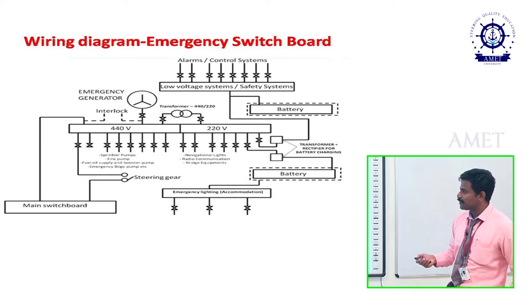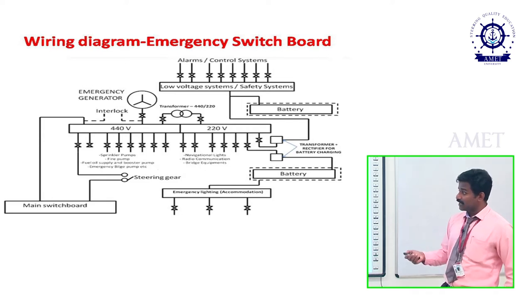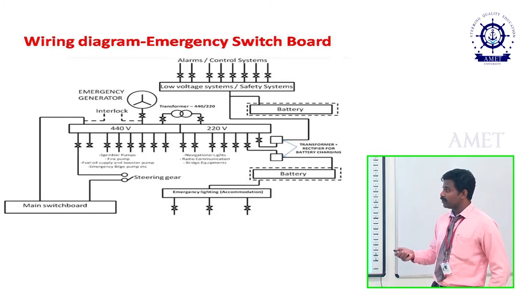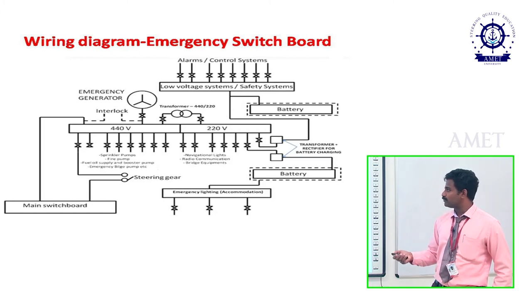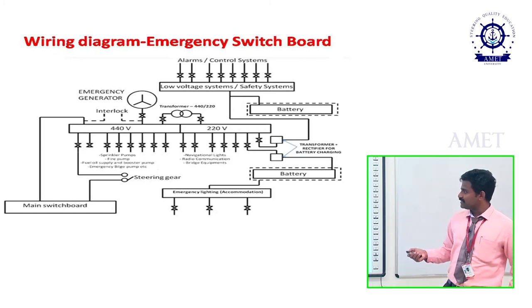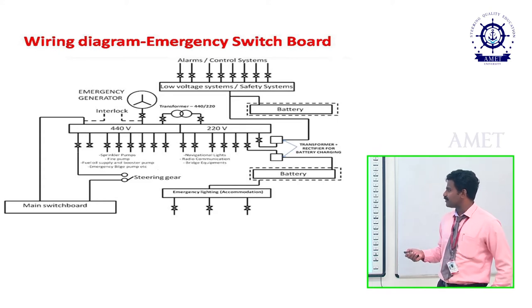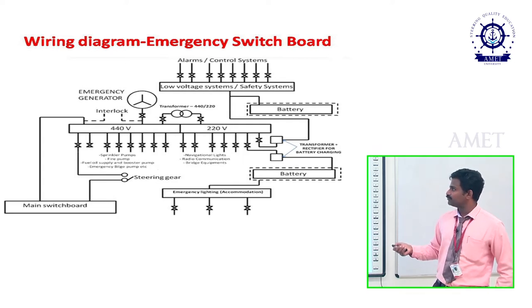For the 440V section, heavy loads such as sprinkler pumps, fire pumps, fuel oil supply, booster pump, and emergency bilge pump are connected. These are heavy loads that require 24-hour supply. For the 220V section, navigational lights, radio communication, and bridge equipment are connected — 220V is sufficient for these purposes.